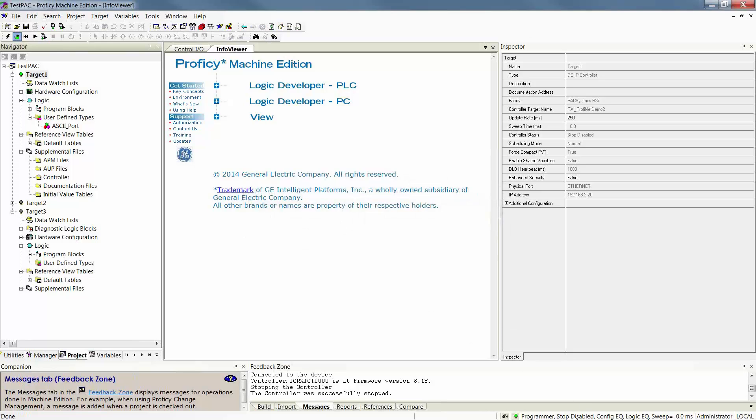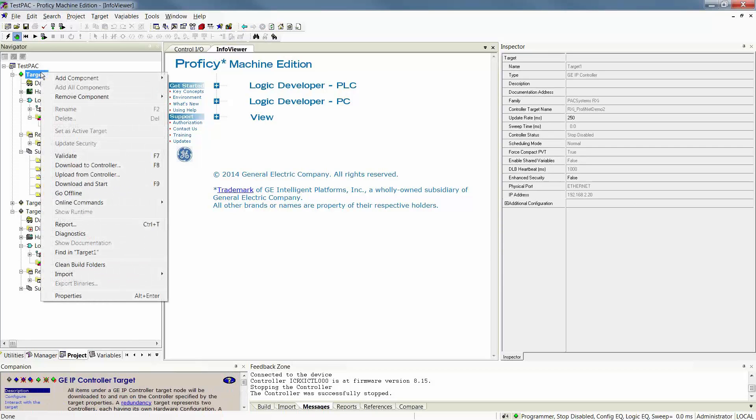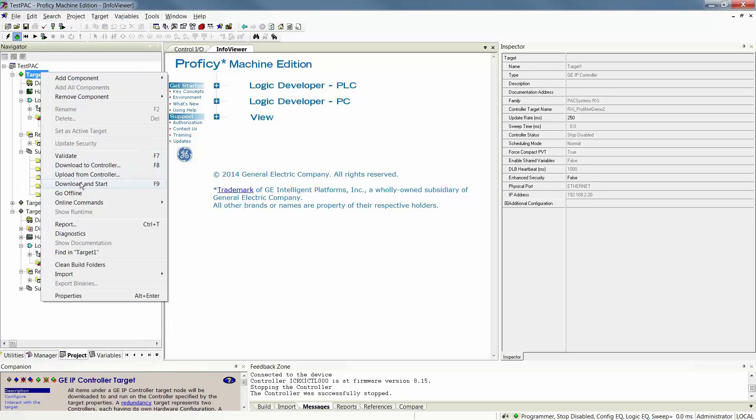Again, the state of your controller is going to show in the lower right-hand corner of your Machine Edition window. I can now download if my configuration was not equal. If it is simply my logic that is not equal, I can in fact do a download while running.